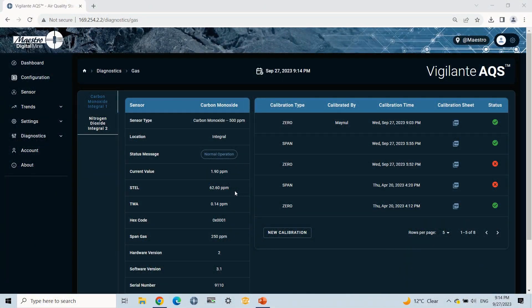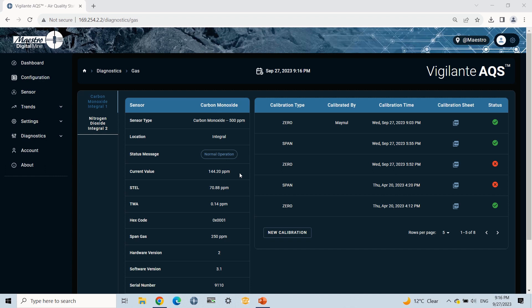Once everything is connected, make sure that the calibration cup is properly connected to the sensor. On the Gas Sensor Diagnostics web page, you can see the real-time value is increasing. Wait until the real-time value comes near to our span value.